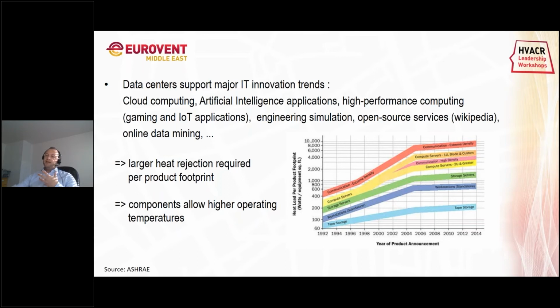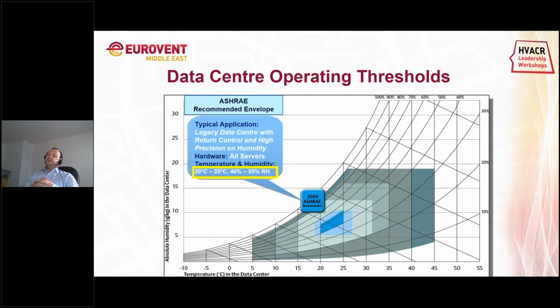Then we have to go to the beginning. Initially, data centers were using quite low temperatures. But when they started getting bigger and bigger, they saw that the energy costs were always increasing, and they were thinking of having higher temperatures inside the data center. In 2004, ASHRAE gave a guideline to the industry, and the recommendation for data centers was to have a server inlet temperature between 20 and 25 degrees Celsius.